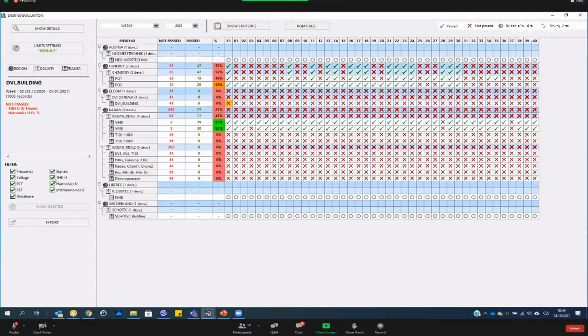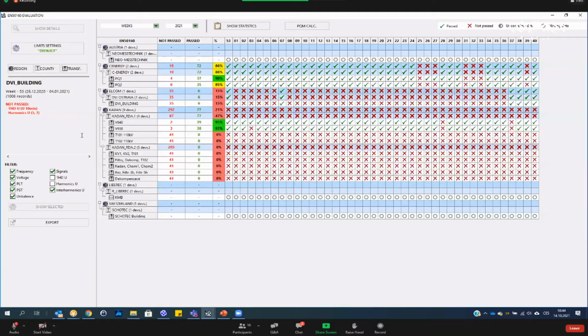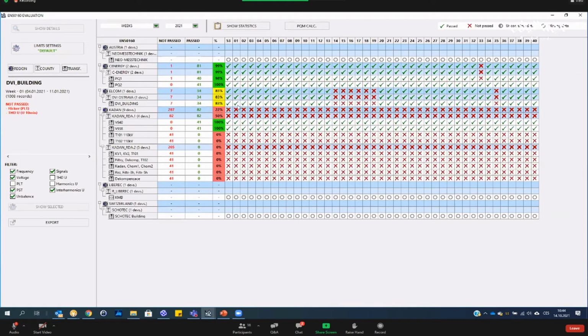I'll disable THD and harmonics in the evaluation, and then I can simply see that the flicker in our building is also out of the limits. Unfortunately we have quite bad quality, but the first weeks of this year all passed. Then in weeks 14 and 15 it failed again, and when I click on it, I can see that the short time flicker didn't pass.